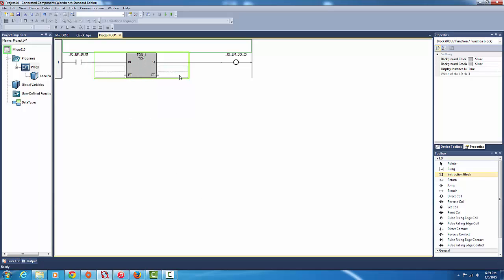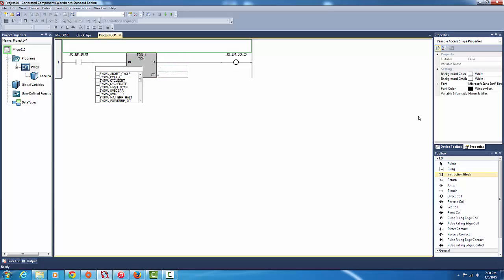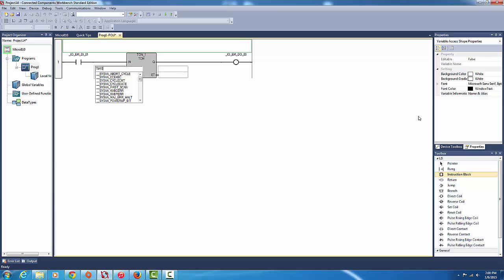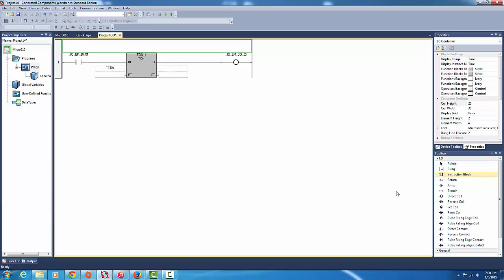So we don't touch this one. I think if you try to touch this one it's just going to start from timer input and I don't know why, what's the point of that when you want it to always start at zero. And preset time has a weird syntax to it: T hash and then how many seconds you want. For this I'll put 10 seconds and S for seconds.